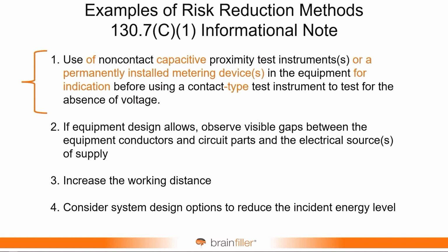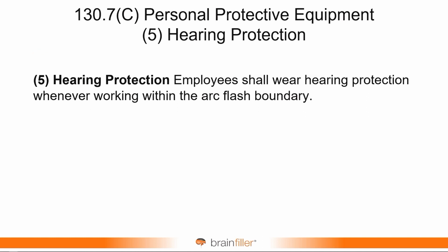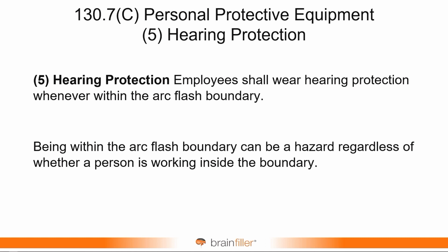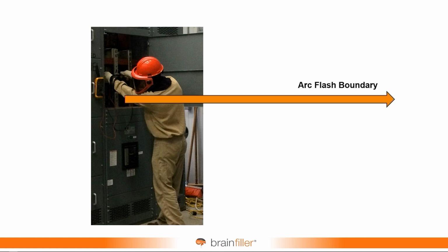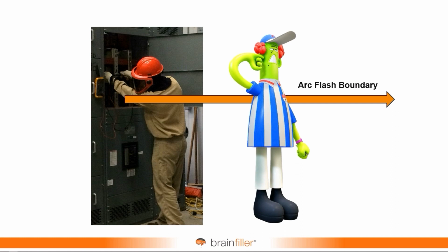Items 2, 3, and 4 remain unchanged. Hearing protection. This is kind of interesting. With hearing protection, you're required to wear it whenever working within the arc flash boundary, but it was recognized you don't necessarily have to be working within the boundary. Just being within the arc flash boundary presents the hazard. So the term working was removed. Basically, if you are within the arc flash boundary, whether you are working or not, you have to have hearing protection. And sticking your finger in the ear doesn't count for hearing protection.